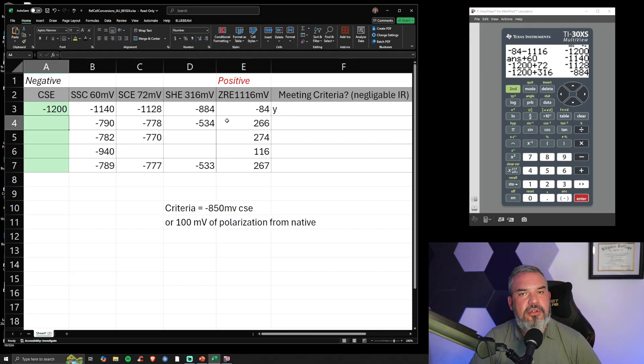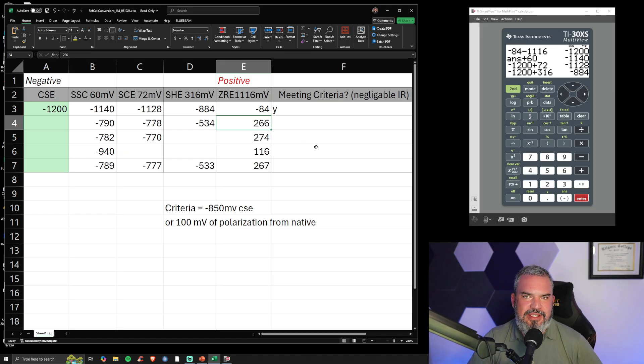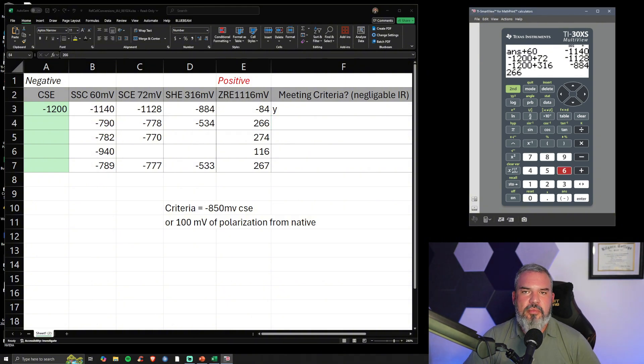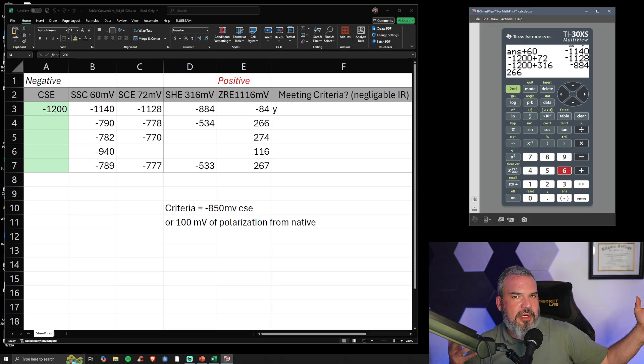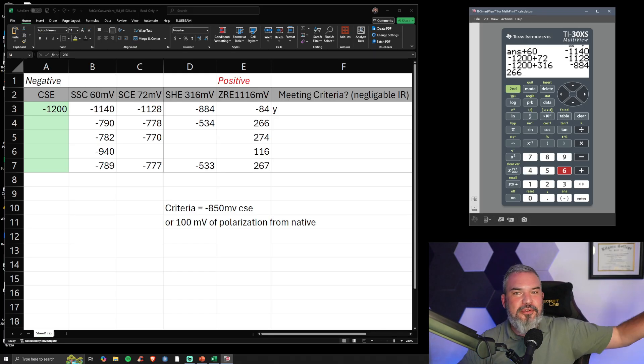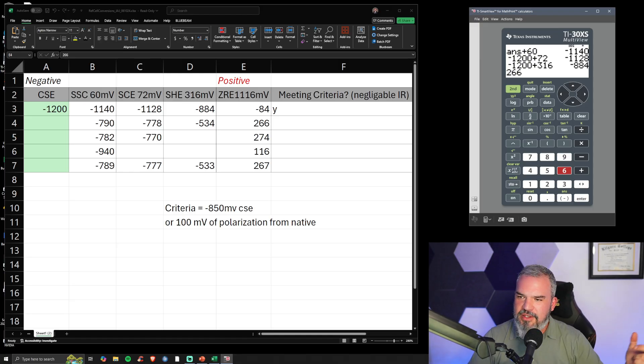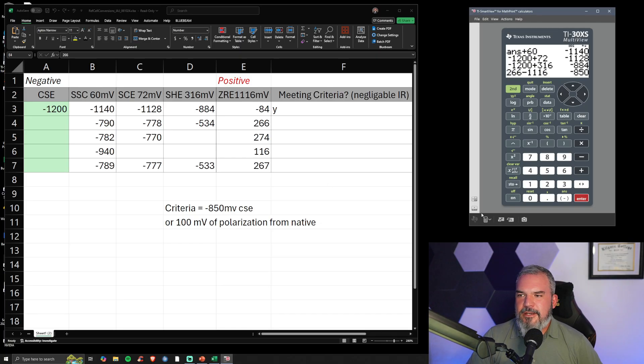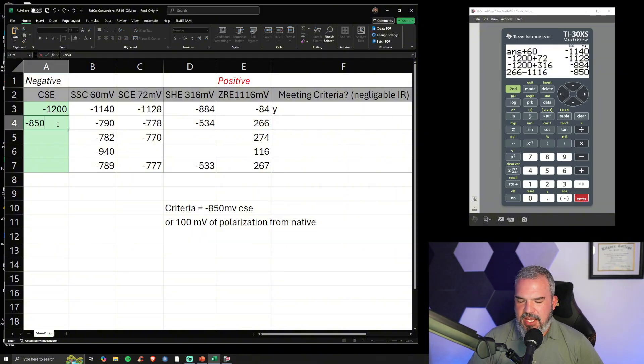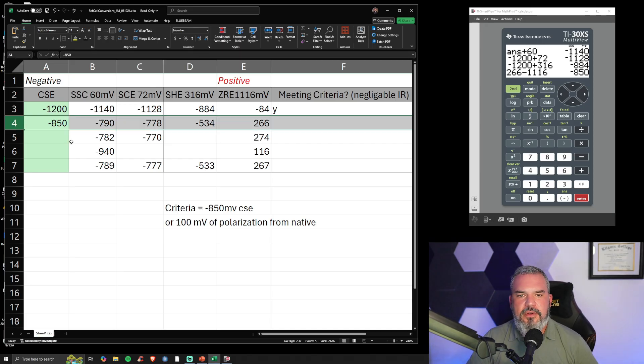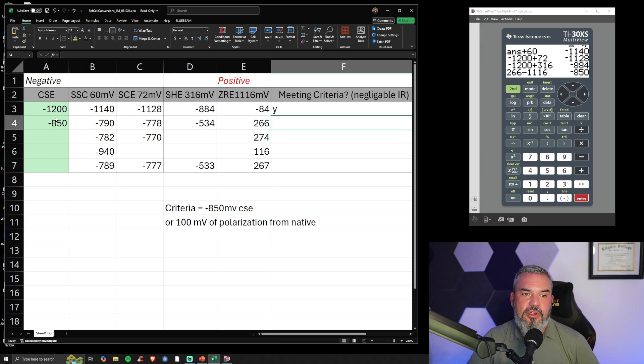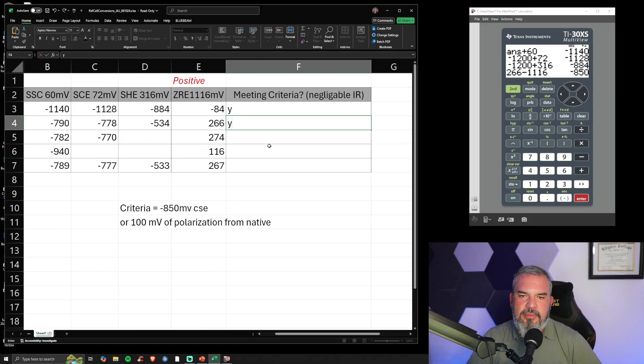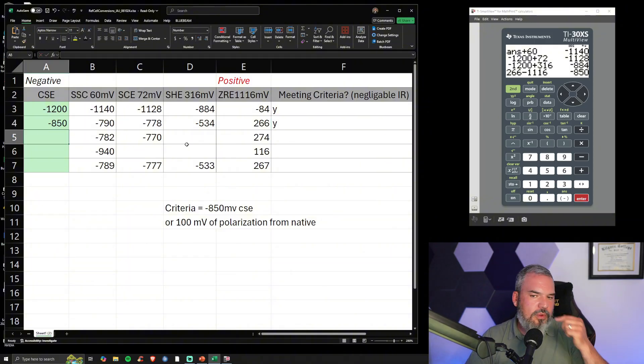Row 4: I've taken a pipe-to-soil with zinc and got positive 266 millivolts. To convert to copper sulfate, I'm going more negative — subtract 1,116 millivolts: +266 − 1,116 = −850 millivolts. That gives us −850 mV at CSE. Assuming negligible IR error, we meet the −850 mV criterion. Life is good.